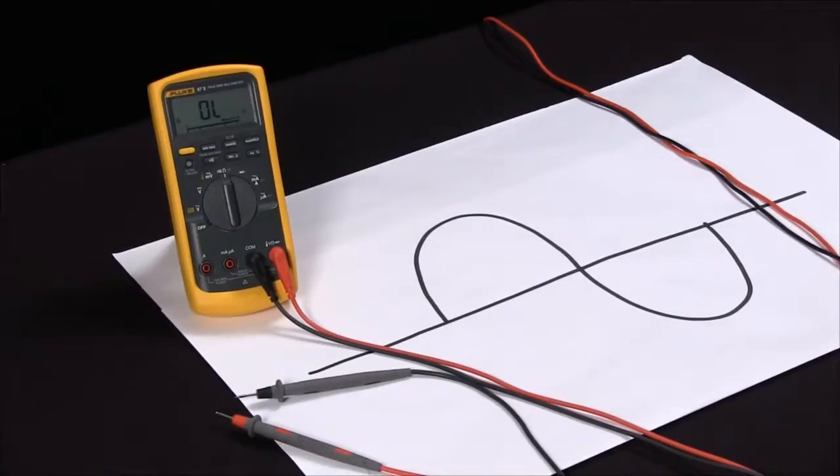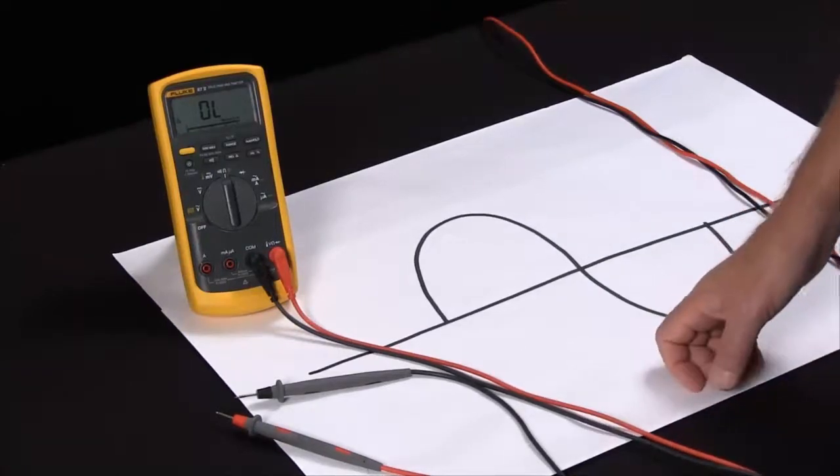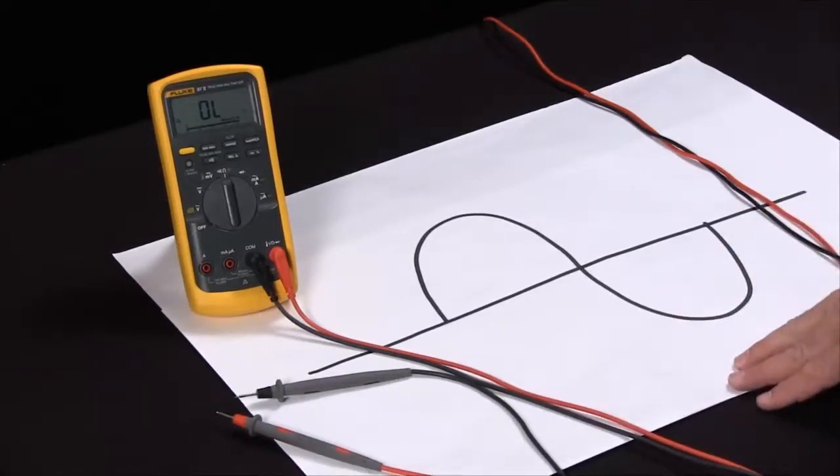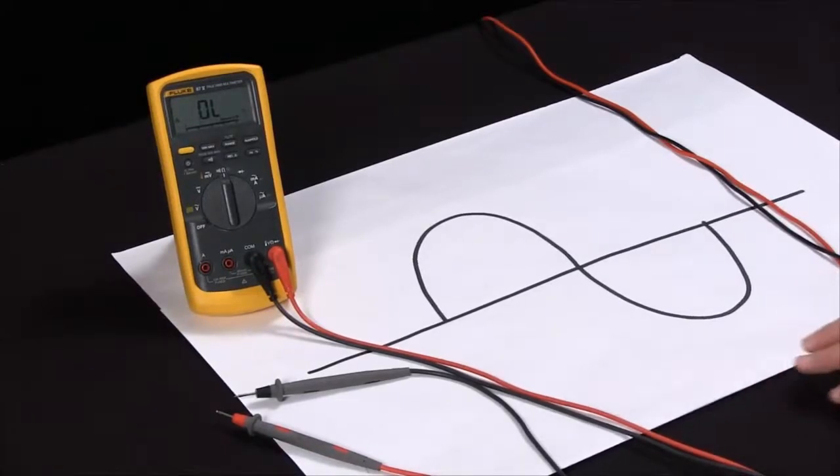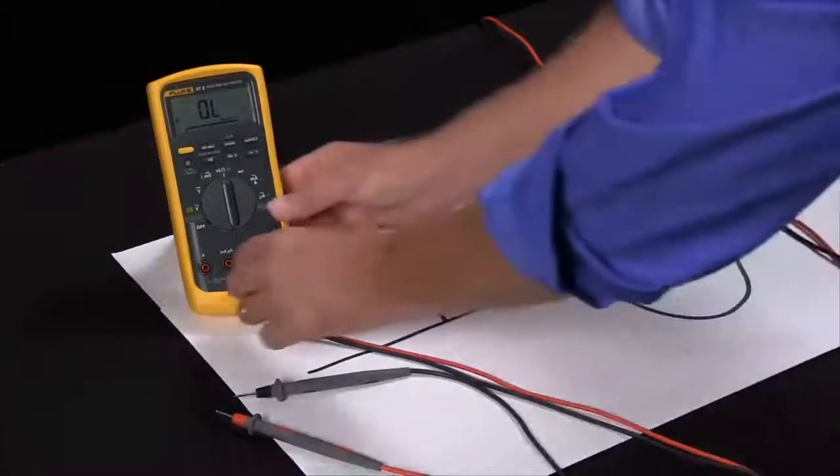I can go to the source, hit the relative mode, it goes to zero. If I then go out to the load and I read minus 10 volts then I know I have a 10 volt voltage drop between the source and the load. So that can be a very handy function.